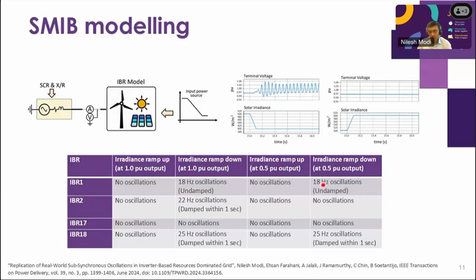There was some other interesting observation we also noticed in the modeling exercise. There was another IBR showing a very brief excursion of 22 Hz oscillation, but it was damping down within a second or so. Similarly, there was one IBR which has a 25 Hz mode, but it is well damped. And later on, Shahil will probably show you that there is a well damped 22 to 23 Hz mode in that part of the network as well.